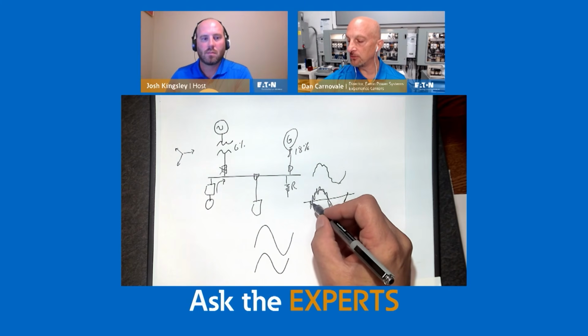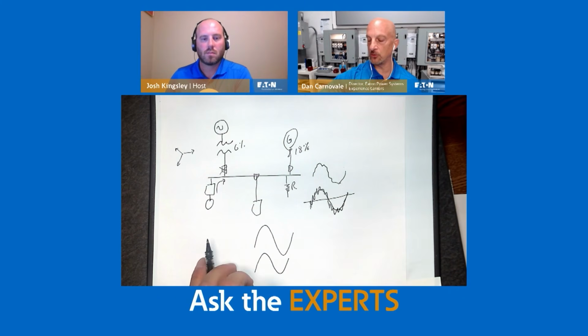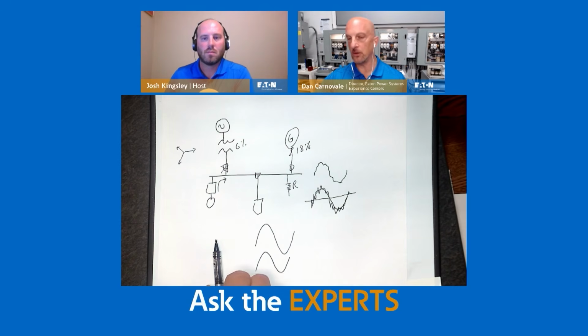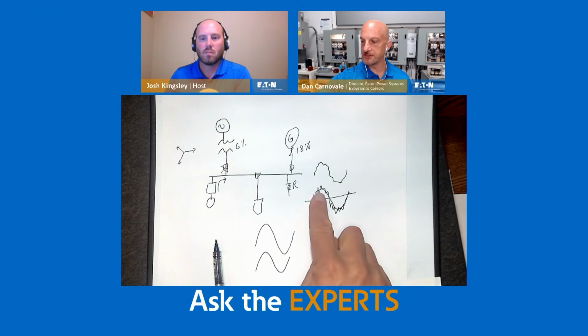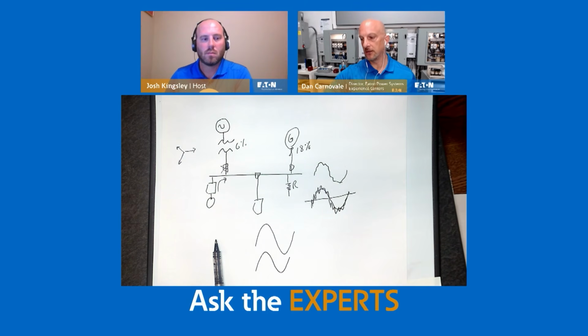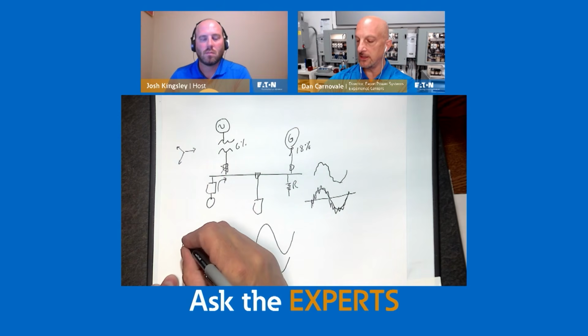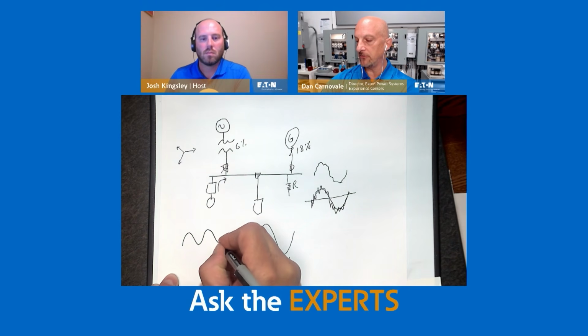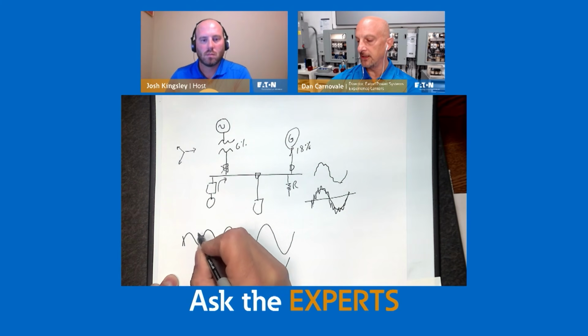What I mentioned over here with multiple zero crossings is I had an example where somebody was using a welding line in an auto plant, and the stamping presses they were running were causing enough voltage distortion on the system to cause the welder, instead of being 20 cycles long, the weld was 8 cycles. They were counting. A nice way to keep track of time, by the way, is if you're looking at a sine wave, every time it crosses 0 here and then back here again, that happens to be 16.67 milliseconds.